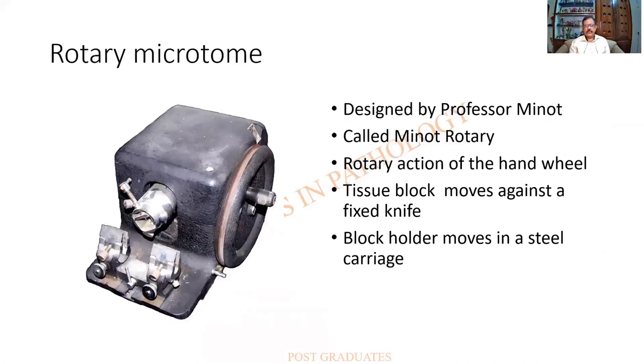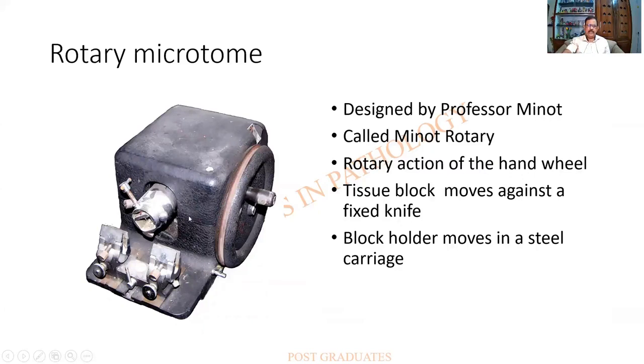The second type is the rotary microtome. Spencer's was one of the companies; it was designed by Professor Minot and hence called the Minot rotary microtome. There is an adjustment which rotates — hence the name rotary — and as it rotates, the block holder moves forward and up and down against a fixed knife. The block holder is attached to a carriage behind it.